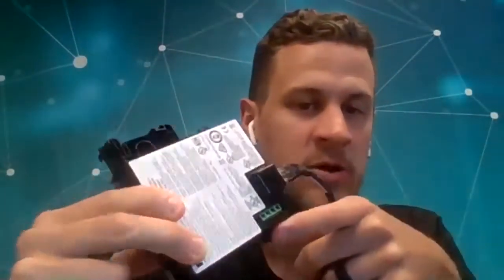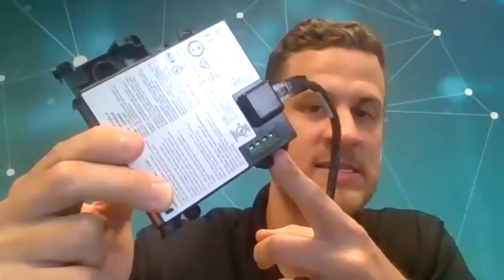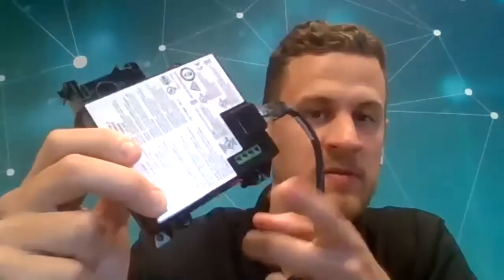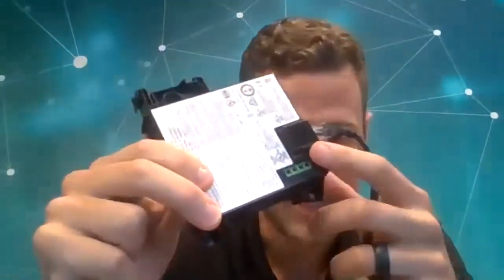This isolation module has a long set of sensor leads. This is what gets installed to your 3-phase or wherever you're installing this. It has 2 sensor leads per phase to verify connectivity, which I'll show in the demo unit here as well. And then the final thing it has is a set of output contacts right here. These green output contacts are part of the functional safety system. They're normally open and they will close when you verify absence of voltage and get the green LED. And I'll show you a really cool use case in my demo unit here.